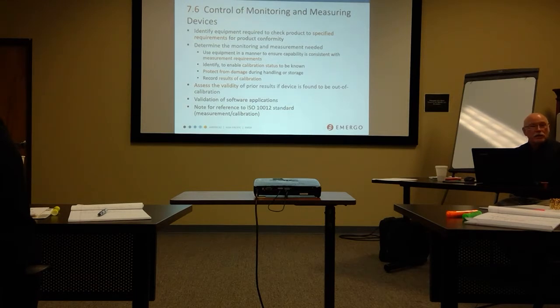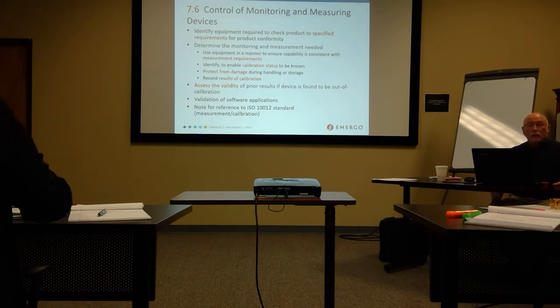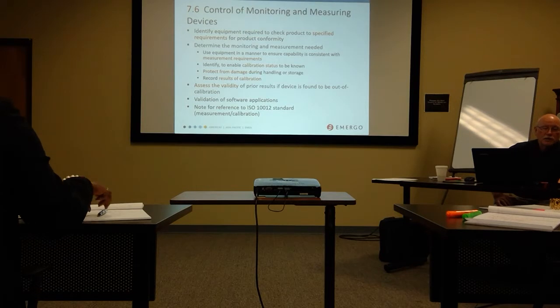How do you manage this? You have an Excel spreadsheet, you have software, there's a number of different, most of these are relational databases. Those have to be validated. Lots of things to pay attention to. Now, regardless of how you do your calibration, it is critically important that somebody looks at those results when they come back, whether it's done internally by your own people, or external.